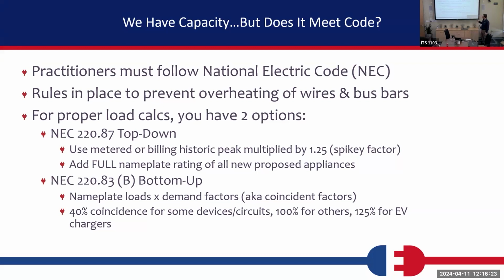There are rules in place, and the National Electric Code is focused on safety. We don't want to be pulling too much current through the wires. So the rules and requirements for load calculations are in place to prevent overheating of the wires and bus bars - we want to avoid shock hazards and fire potential in the house. Because of that, we can't just take the total large remaining capacity available from some of those previous charts; we have to follow the right rules and procedures.